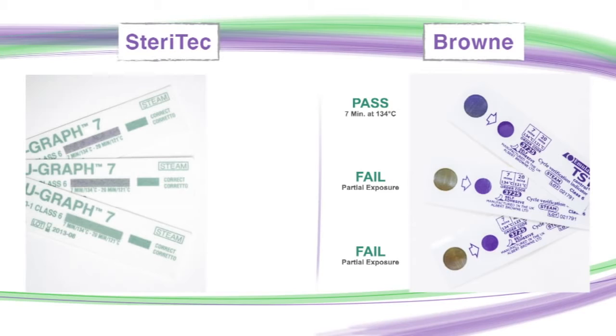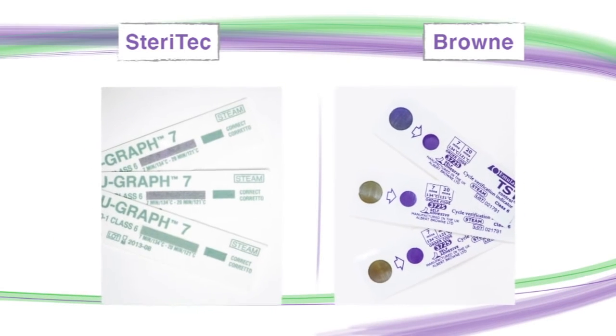These SteriTec tests have also been exposed in an autoclave. The bottom indicator shows a clear pass result as indicated by a complete purple to green color change. The top two tests have been partially exposed. They have clearly been through a failed sterilization cycle as indicated by an incomplete color change. All of these tests would now be kept and archived after recording either a pass or fail result.